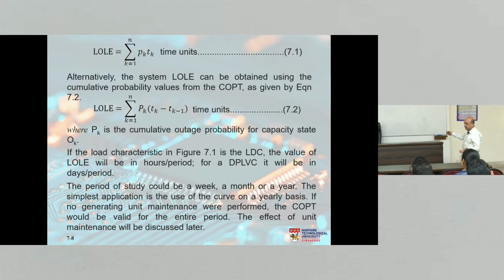If the period is a year, hours per year. If the period is a month, hours per month, and so on. And for a daily peak load variation curve, it will be in days per period, obviously, correct? And the period of study could be a week, a month, or a year. And we could even include generator maintenance and generators being decommissioned, new generators being added. We can include all of that in a more detailed study.